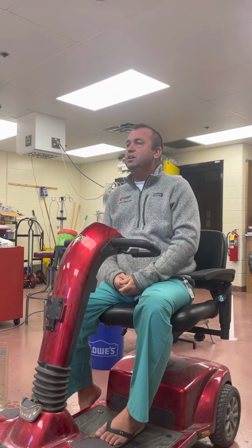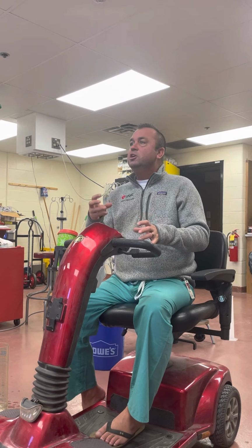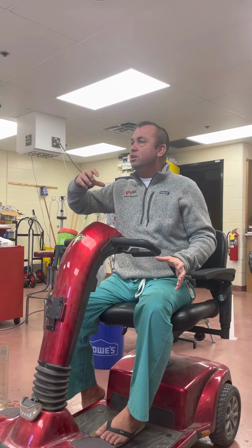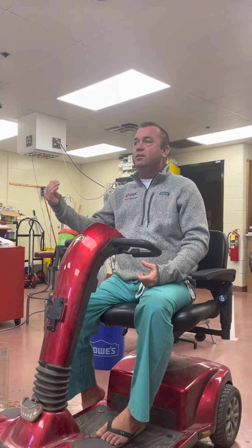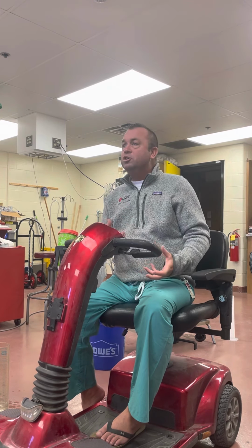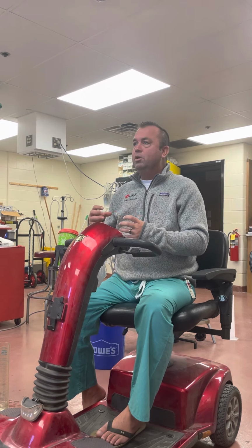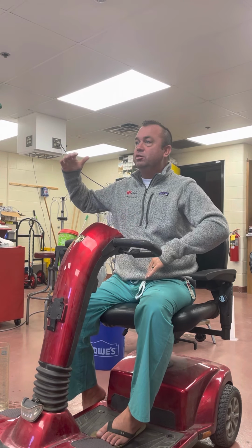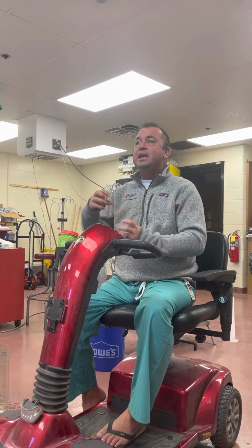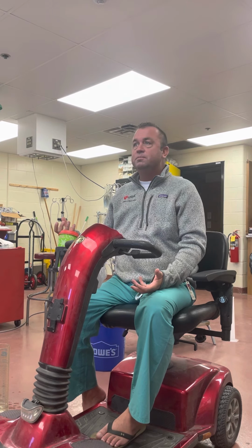Kinetic-assisted venous drainage is where you use an actual pump in the venous line. So as you would turn that pump up, it would increase the negative pressure on the venous line, and thus as RPMs on that pump go up, your negative pressure goes up, and flow increases down our venous line. The same thing happens with larger tubing, or the height gradient increases. So as radius increases, as the height gradient increases, negative pressure on that line also increases, which pulls more volume. That's what we saw, correct?